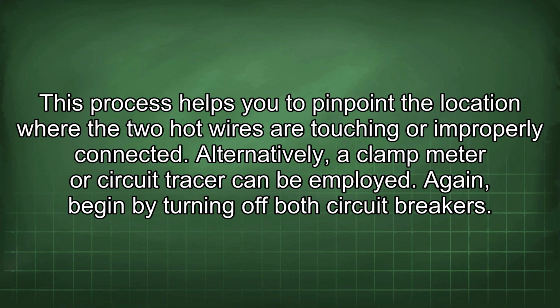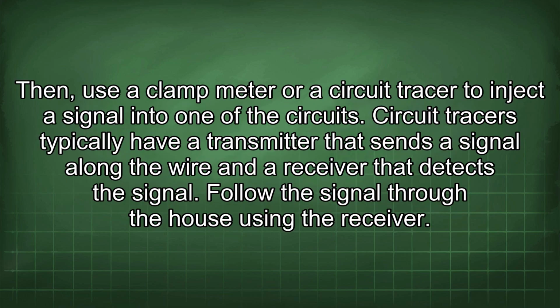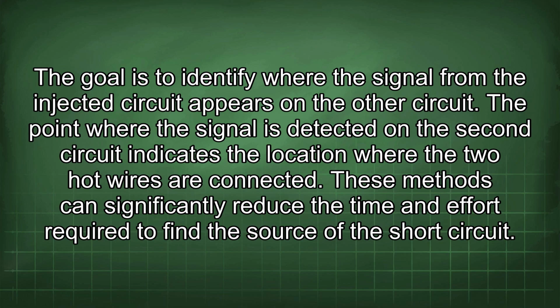Alternatively, a clamp meter or circuit tracer can be employed. Again, begin by turning off both circuit breakers. Then, use a clamp meter or a circuit tracer to inject a signal into one of the circuits. Circuit tracers typically have a transmitter that sends a signal along the wire and a receiver that detects the signal. Follow the signal through the house using the receiver. The goal is to identify where the signal from the injected circuit appears on the other circuit. The point where the signal is detected on the second circuit indicates the location where the two hot wires are connected. These methods can significantly reduce the time and effort required to find the source of the short circuit.